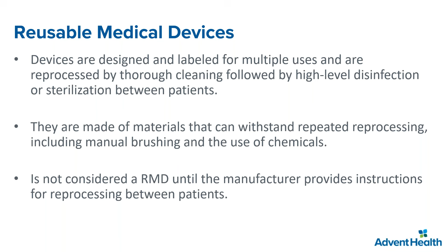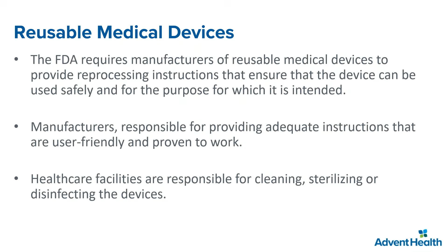They are made of materials that can withstand repeated reprocessing, including manual brushing and the use of chemicals. It's not considered a reusable medical device until the manufacturer provides instructions for reprocessing between patients. So the FDA, the Food and Drug Administration, requires the manufacturer of reusable medical devices to provide reprocessing instructions that ensure that the device can be used safely and for the purpose for which it's intended. The manufacturer is responsible for providing adequate instructions that are user-friendly and proven to work. However, this point is very important because the healthcare facilities are responsible for cleaning, sterilizing, or disinfecting these devices.